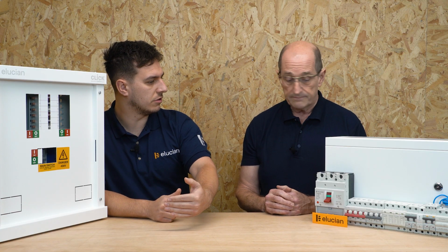So I've heard a term as well, inrush current. Is that what you're referring to? That's what we're dealing with. Yeah. So let's say, for argument's sake, we've got some lights above us here, we've got some lights in the studio. When we're switching them on, they're going 2-3 times the rating of the protected device upstream of it. So let's say the lighting, you've got a 10 amp device protecting it, but when you switch them on, the load could be 2-3 times that of 10.